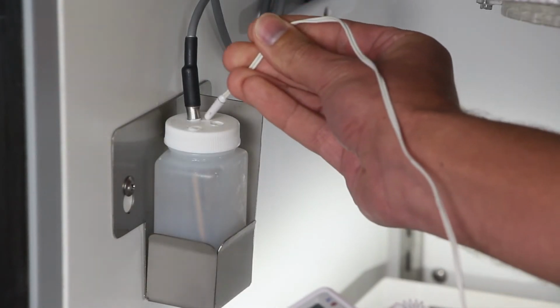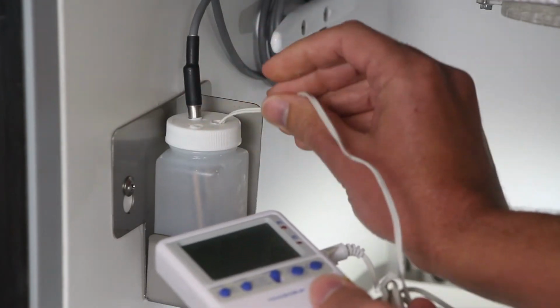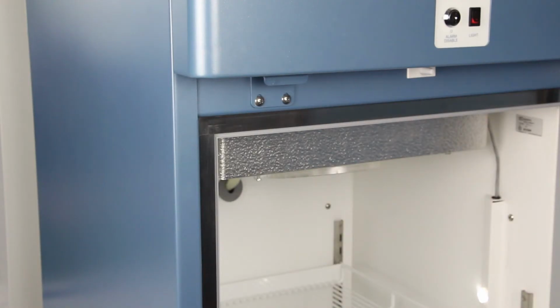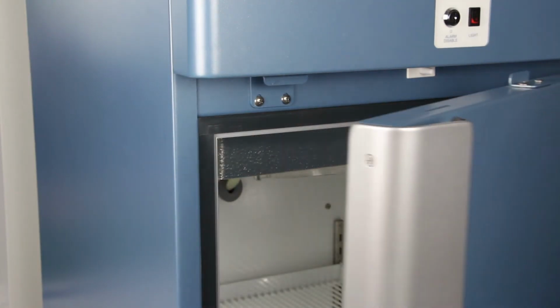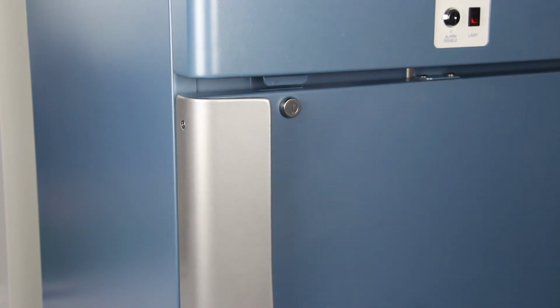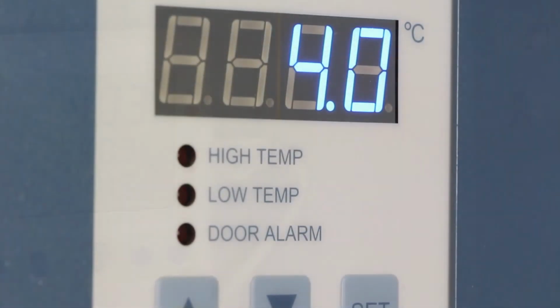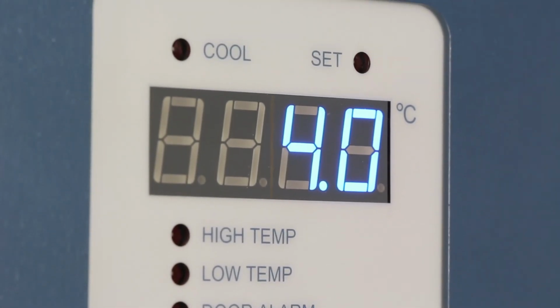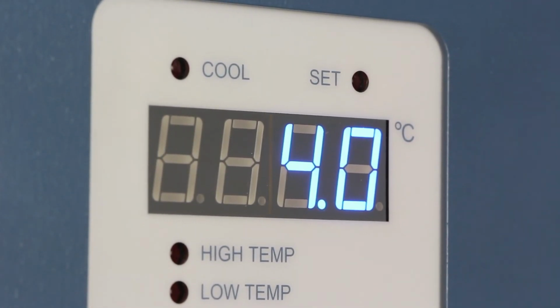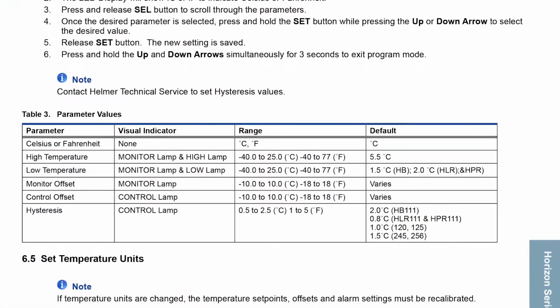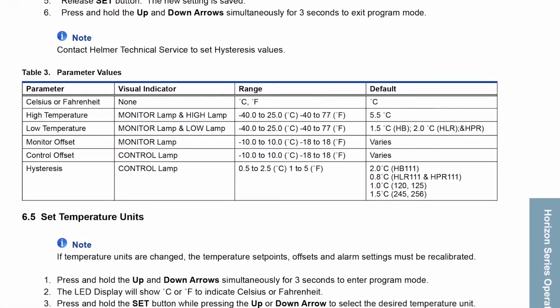We also recommend checking the temperature calibration. This is simply done by placing a calibrated independent thermometer into the probe bottle with our monitor probe and making sure the temperature reading corresponds to the temp reading on the display. If the calibration is off, or if the unit does not stabilize at the correct temperature, adjustments can be made to the settings to correct this.